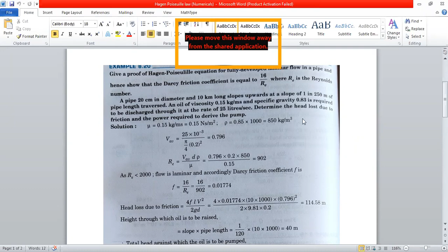So L is 10 kilometer, we convert it into the meter. So here 10 into 1000, that converts into meter. 10 into 1000, that means 10,000 meter long, into V square 0.796 square by 2 into g 9.81 into 0.2, that is equal to 114.58 meter. So head loss due to friction is 114.58 meter. Okay, so determine the head loss due to friction and the power.